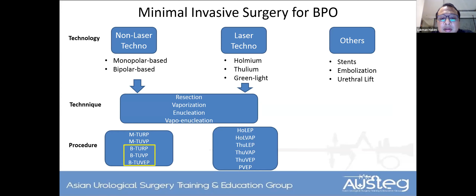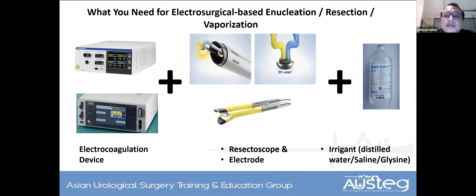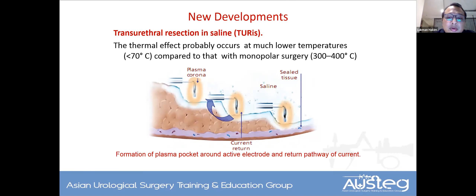The bipolar device is usually high frequency, and then we also need a resectoscope and its electrode. And the resectoscope or electrode is different between the monopolar or bipolar device. And third is the irrigant. We can use distilled water, saline, or glycine for surgery. Now, the so-called transurethral resection in saline, or on the other hand, also called bipolar TURP, is basically, as I mentioned earlier, constituting a very low temperature surrounding the area, less than 70 degrees Celsius, compared to monopolar, which may trigger 300 to 400 degrees Celsius. This is very important because the surrounding tissue damage can be much prevented using the bipolar technology compared to monopolar.